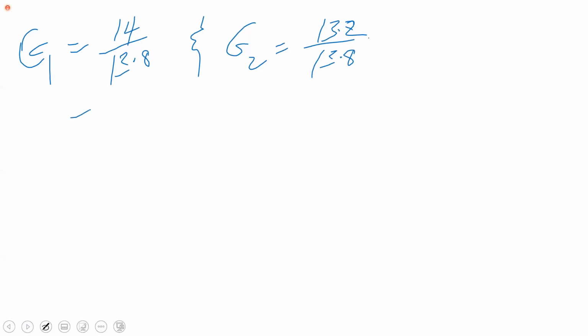I think this one worked out to 1.0145. Some of you may have seen me just circle the generator because you had no value there, you just put back the generator without the value. You have to deal with both the reactance and the voltage for your generator. If you look throughout the network, only the generators have the voltage on them; all the other pieces of equipment just have impedance or reactance as well as rating, but for the generators you have the voltage, so you need to put these in.